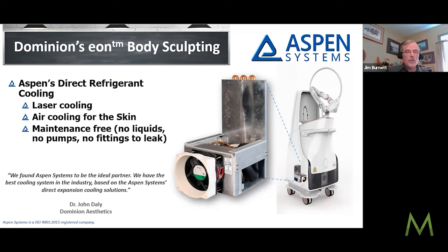We were driven by the requirements, certainly a need for small size. So we took a close look at which style of existing refrigeration compressor would be most amenable to miniaturization. We spent a lot of time on the motor and settled on a rotary vane design, which has been around a long time, but we run it at 6,500 RPM. It's like an Italian sports car using a high RPM small engine, that's the analogy here. A lot of work was done on the motor.